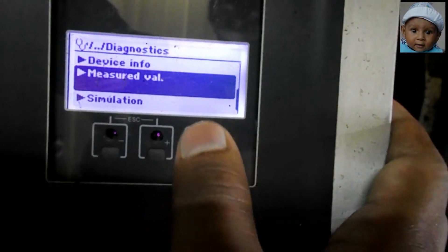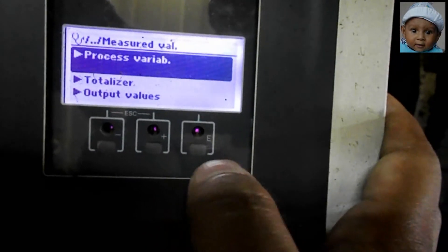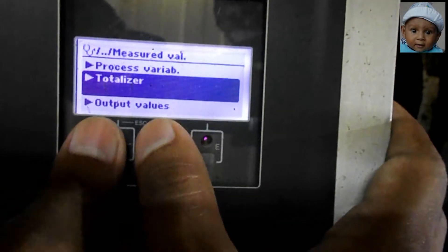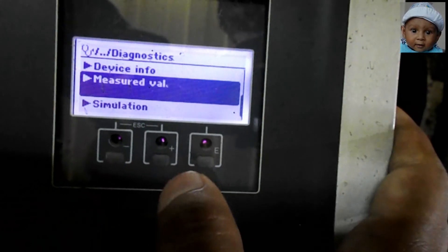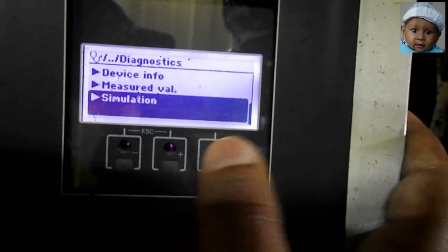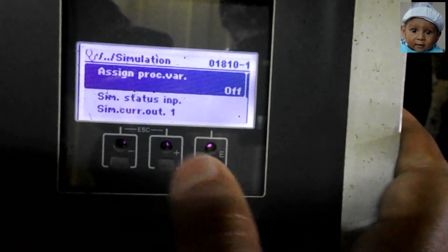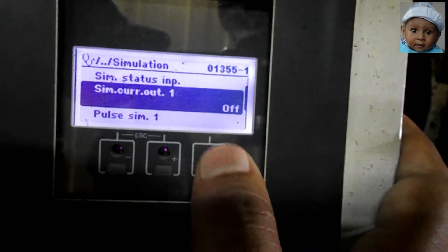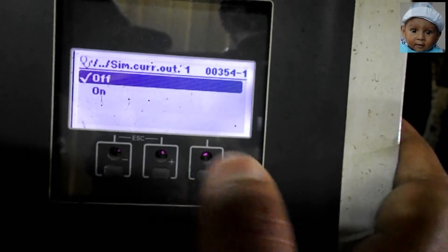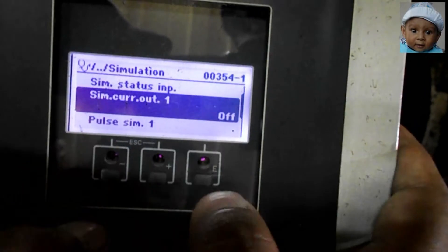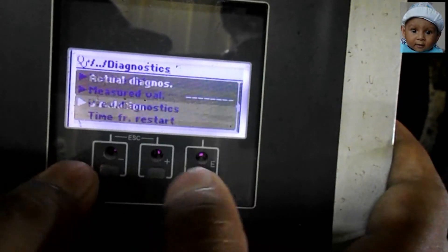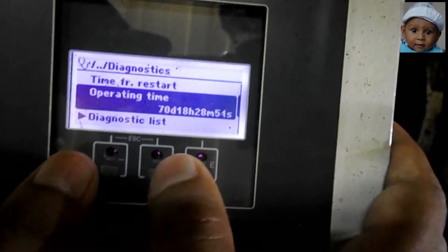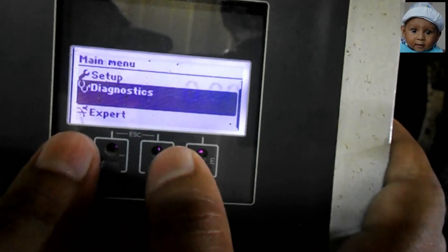If we want to check the signaling in simulation, we have to go to Diagnostic. By simulation mode we can check our PLC programming scaling. Go to Simulation, then Simulation Current Output, and in this parameter we have to turn on the simulation mode.